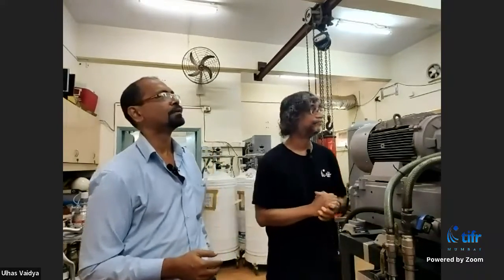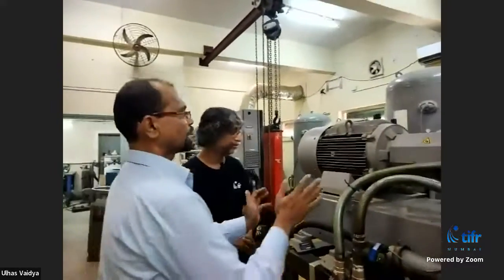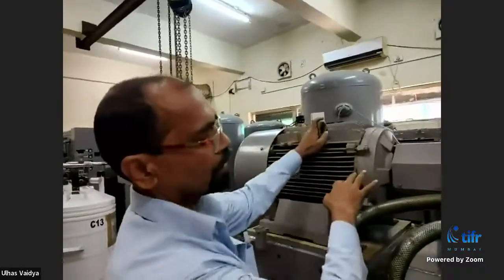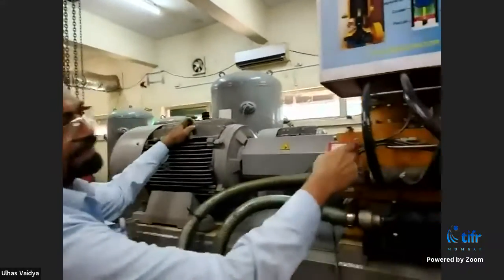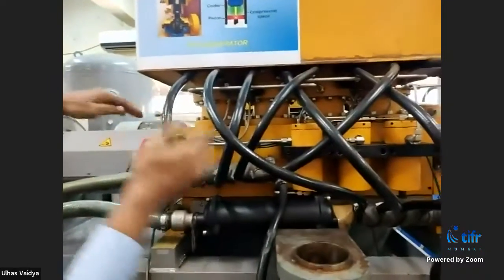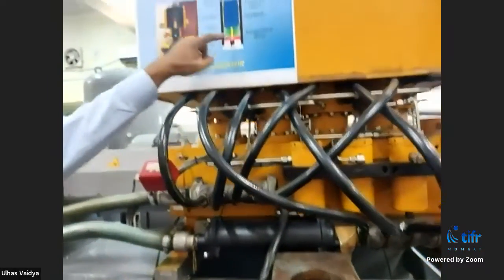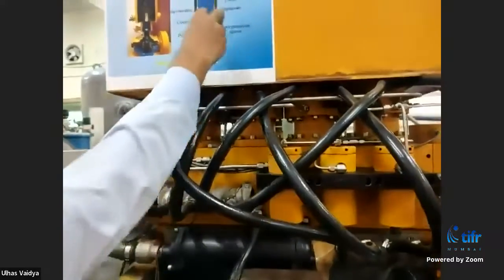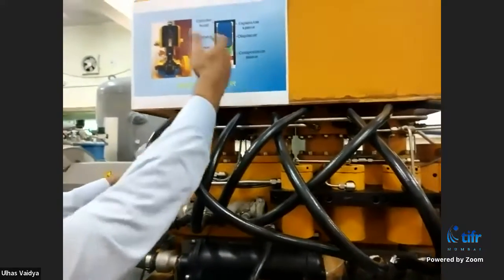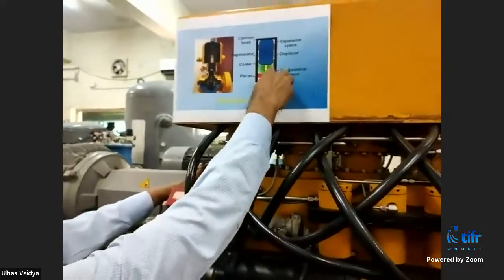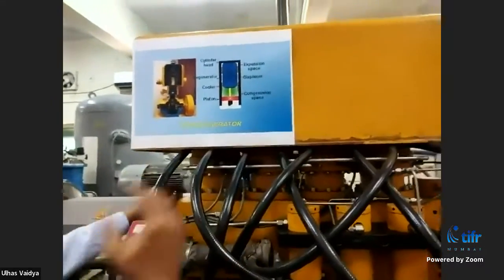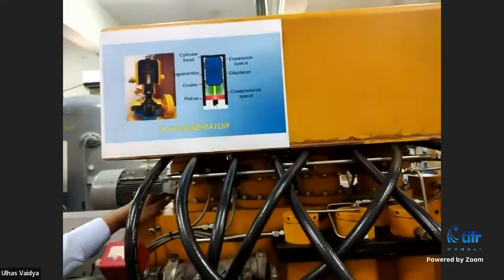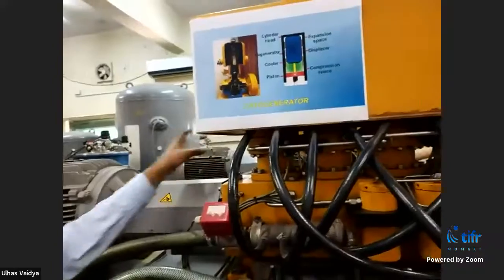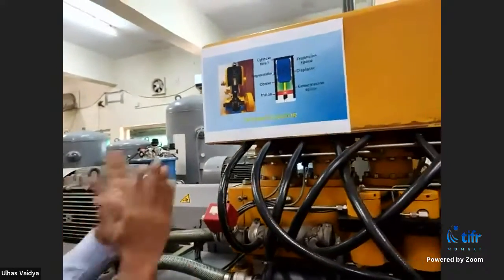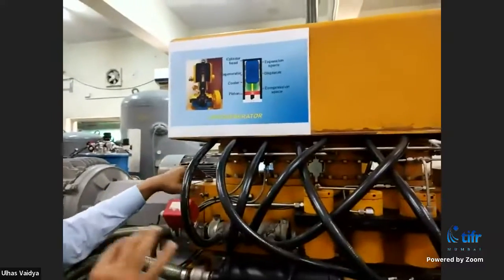Can you tell us more about how exactly this engine works? One more time, like the electrical motor and the other stuff. Okay. So this is a 50 HP electric motor. Then there is a crankshaft which maintains the phase difference of the piston and displacer positions. Then the piston compresses the gas, the helium gas, the working gas. Then it goes to the water cooler where the extra heat is removed, and then you always monitor the pressure of the working gas. This is connected to a PC, and the PC also shows the pressure cycles.